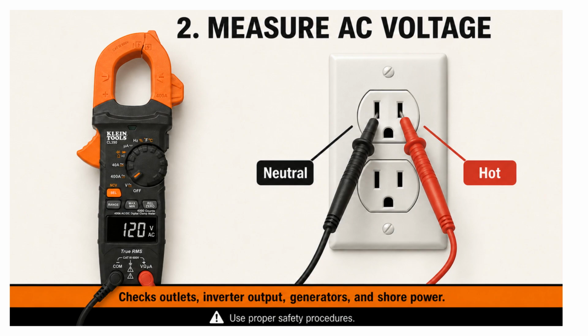AC voltage can injure or kill you. Keep your fingers behind the guards on the probes. Do not touch the metal tips, and do not work inside an energized electrical panel unless you are qualified to do so. A 0 reading does not always mean the power is off. The meter may be on the wrong setting, a probe may not be making contact, or a test lead may be damaged. When a 0 reading matters for safety, test the meter on a known working source before and after checking the circuit.